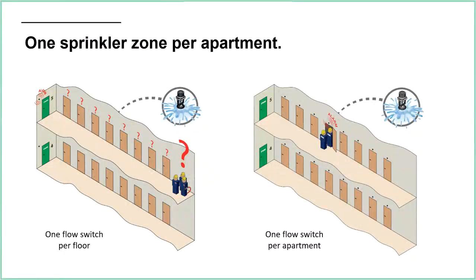The more alarm devices you've got, the more testing you need to do, but the harder it is to do that testing, because you'll have to go down the corridor and discharge water into buckets, or you're actually going to have to get access to the apartments to drain water. So all that will be a hassle, unless, of course, you install our Zonecheck products, where you can do that testing remotely without causing any disruption and without discharging any water. So again, just bear in mind that there is a choice here between one per floor or one per apartment. It's not automatic to have just one flow switch per floor.